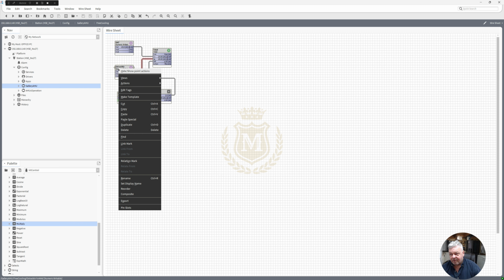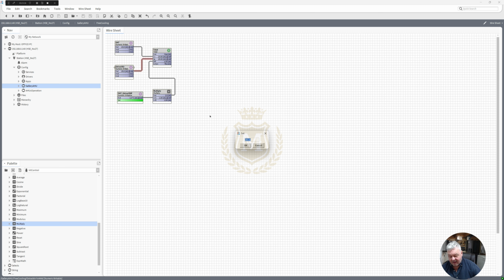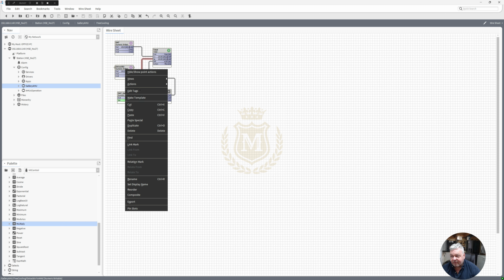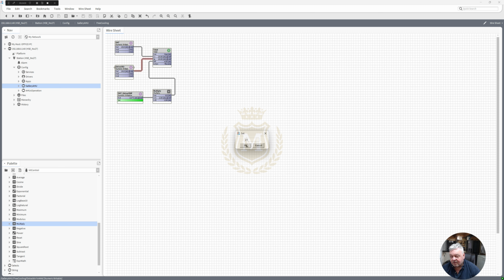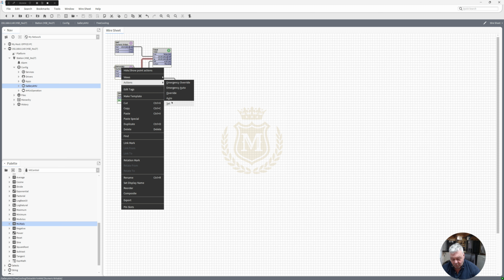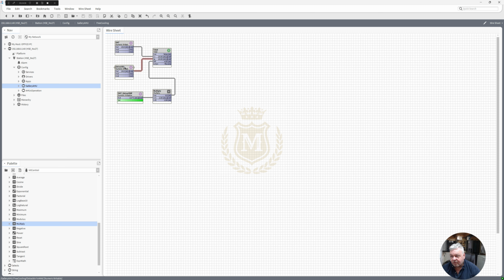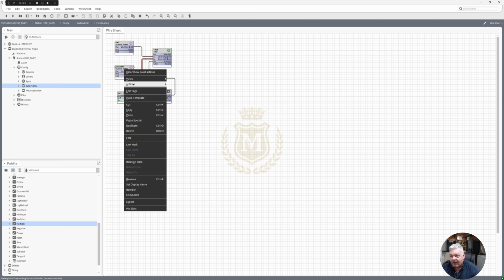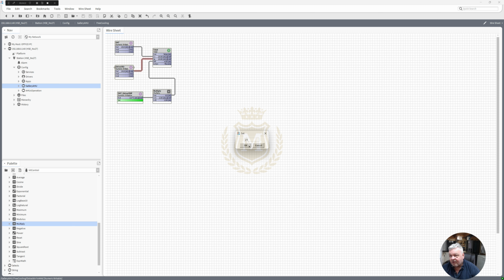So just to show you again, actions, set the extract air to 20 degrees, there is no diff. Actions, set to 24, it will come on this time. There you got your true there. Where when we was at a diff of 2 either side, if I put that now down to action set to 20 and then put that to 24, it won't come on. False. Action set, if I do 24.9, still not on. Actions set 25, on.